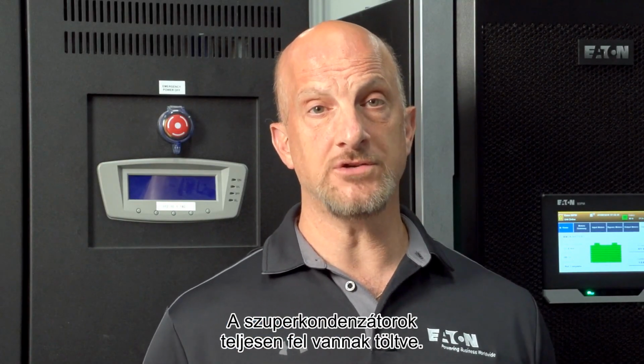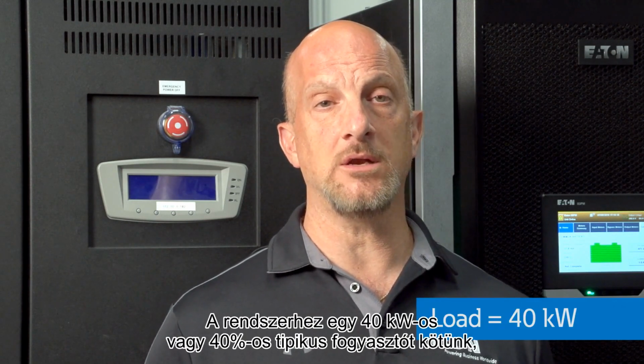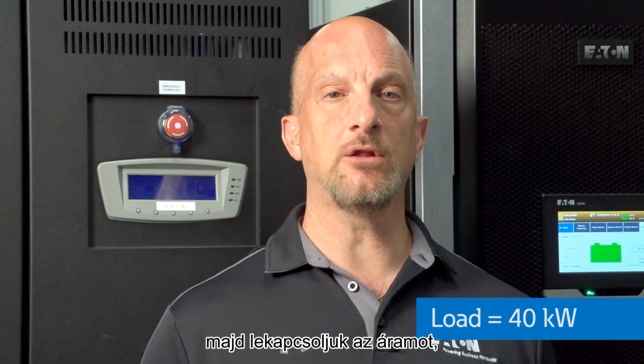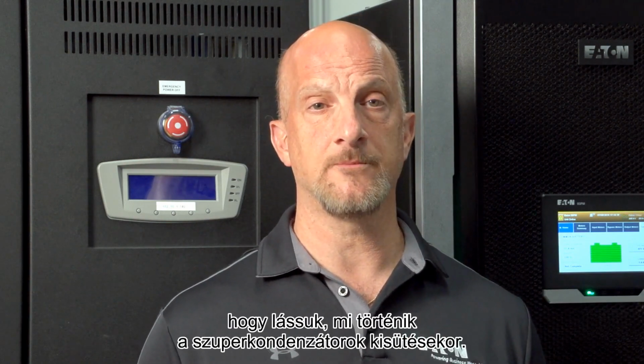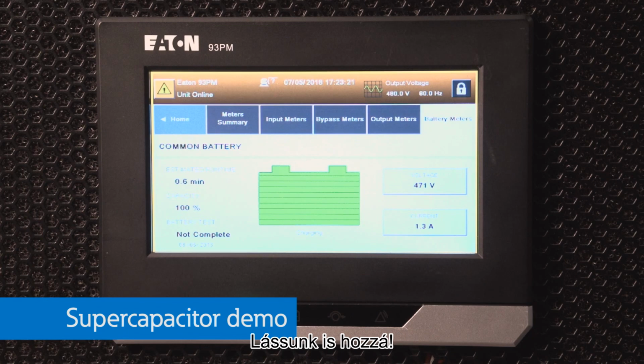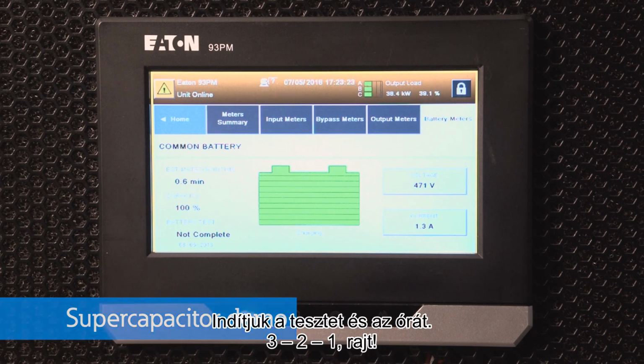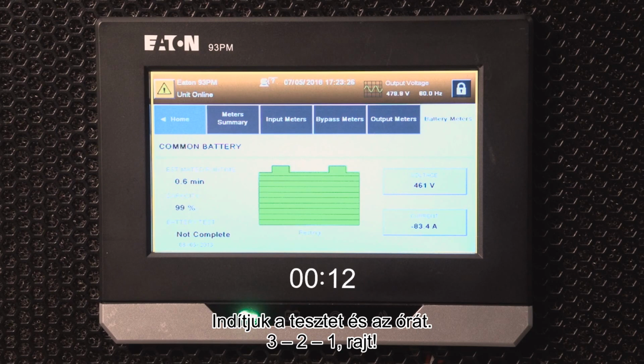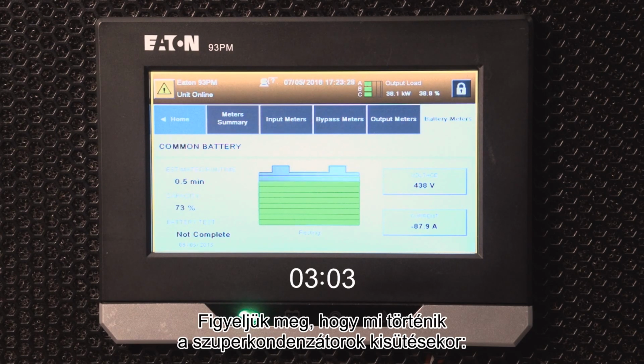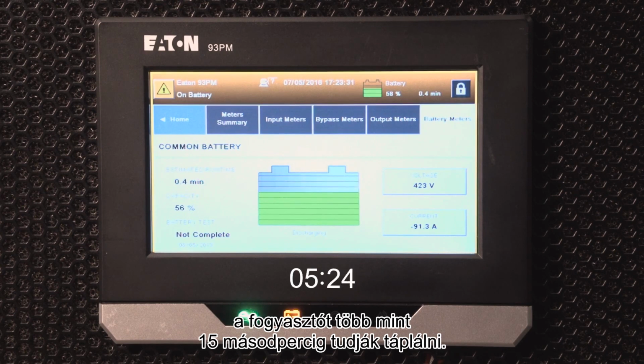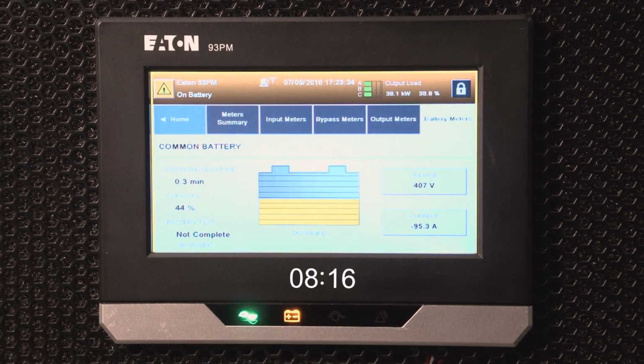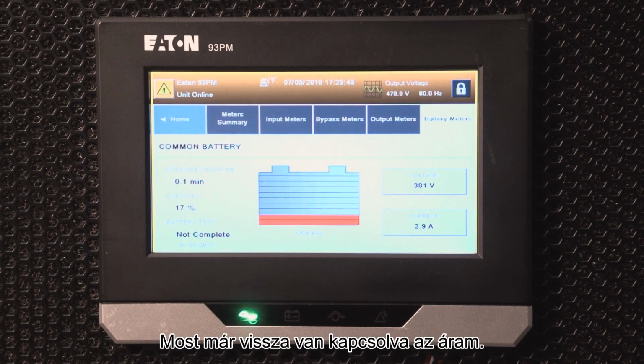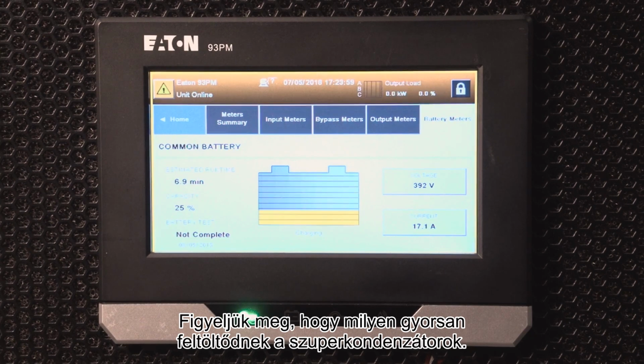The supercaps are fully charged, and we will apply a 40 kilowatt or 40% typical load and then kill the power and watch as the supercaps discharge. Okay, here we go. Initiate the test and start the timer in 3, 2, 1, go. Watch as the supercaps discharge and continue to feed the load for more than 15 seconds. Okay, now the power is back on, and watch as the supercaps recharge very quickly.